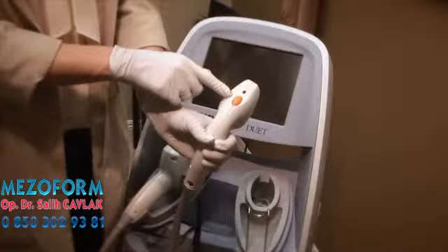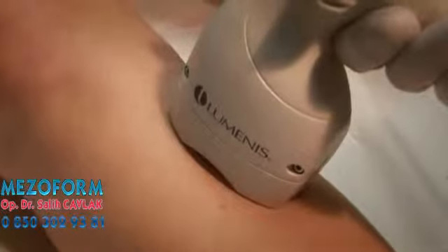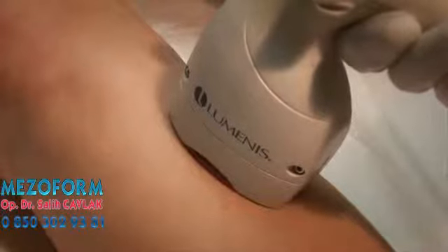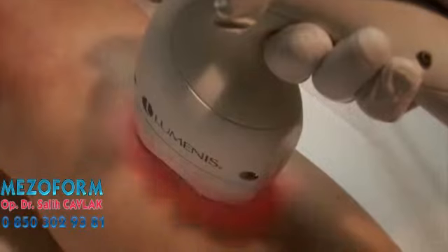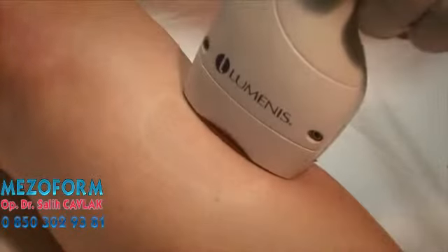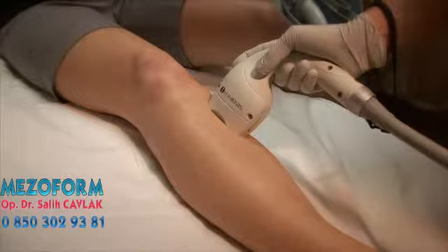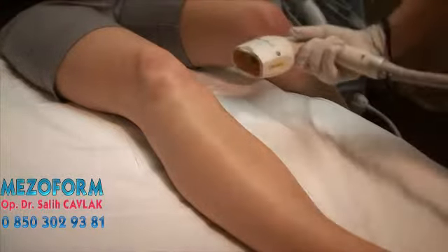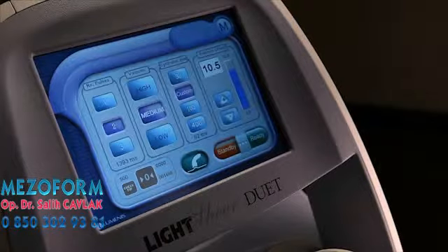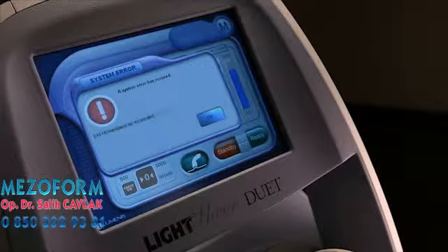Press the handpiece trigger to fire the laser. You'll need to hold the trigger while the device applies vacuum, at which time the laser output will occur. A red flash and tone will indicate the laser has fired. The vacuum will then be released. If the operator lifts off the patient's skin surface prior to the vacuum fully releasing, an error message could appear stating tip error. To avoid this, wait until the vacuum is released before moving the handpiece to the next area being treated.